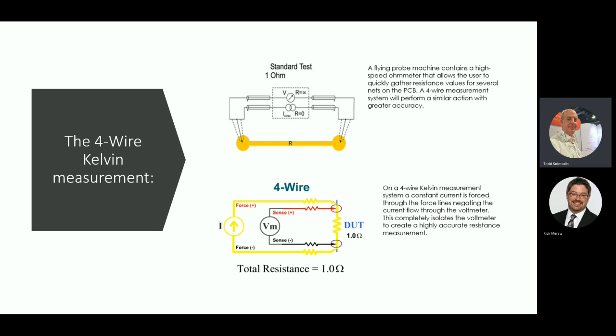That's a great analogy of how the 2-wire and 4-wire work. With the higher resolution 4-wire measurement, if there's a 10% difference—say 0.1 ohm or 100 milliohms—a 2-wire measurement won't show it. You could have a high resolution meter, but you won't see those milli and micro ohm differences with 2-wire. That's why we shunt out the extra lead resistance to get the true measurement.